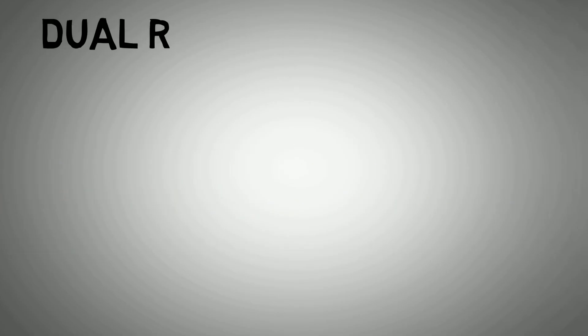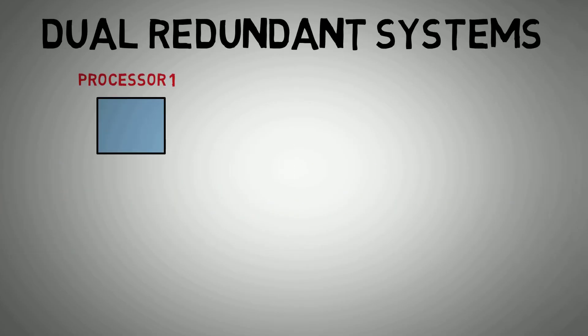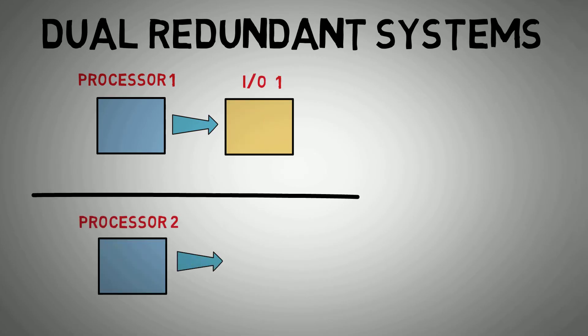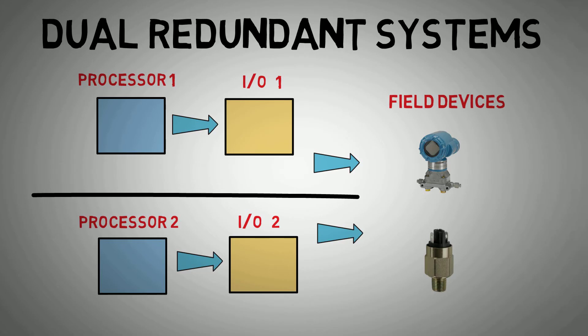Dual redundant systems. For safety applications, you will frequently find dual redundant systems. You may have two sets of processor and I.O. cards that are both supporting the system. You may also have dual processors but simplex or single I.O. counts. It all depends on your specific system requirements.